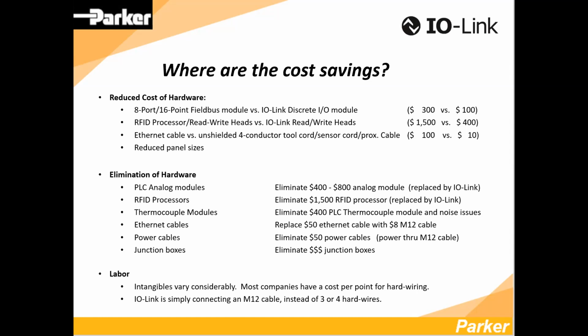How you justify it is by paying less money for the IO-Link equivalent of the fieldbus version. Think about a fieldbus module with 8 ports, 16 points—very traditional. If it's an EtherNet/IP or Profinet module, roughly $300. You can buy the IO-Link equivalent for $100. So if you only have one, you've saved $200, but you haven't paid for your master yet. If you have 3 IO hubs, you've paid for your master. But that's just a discrete IO scenario.